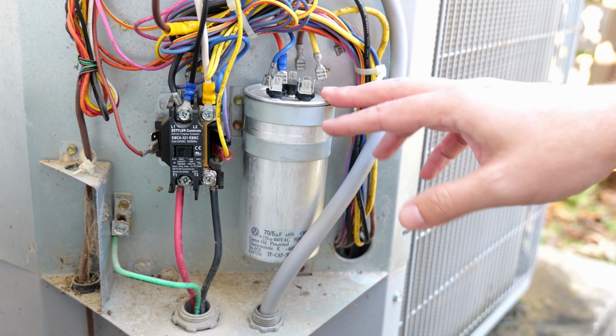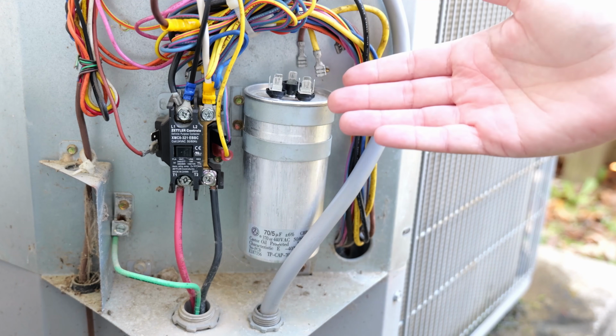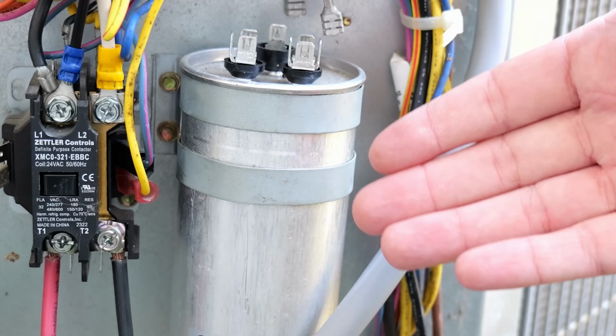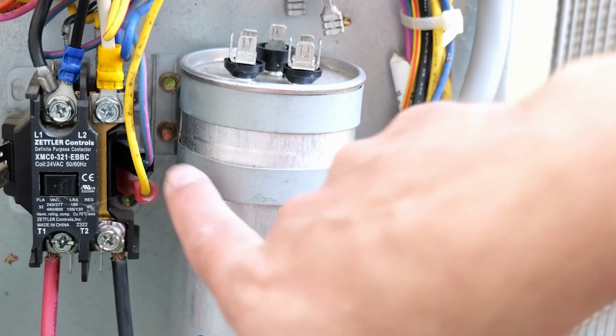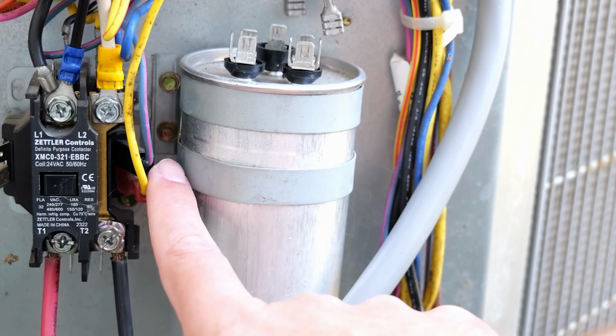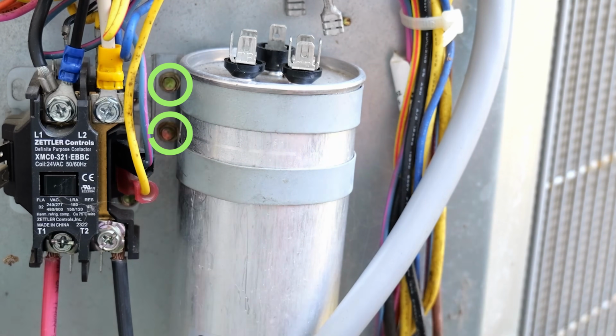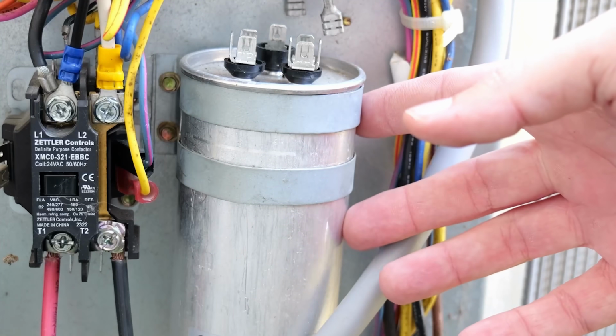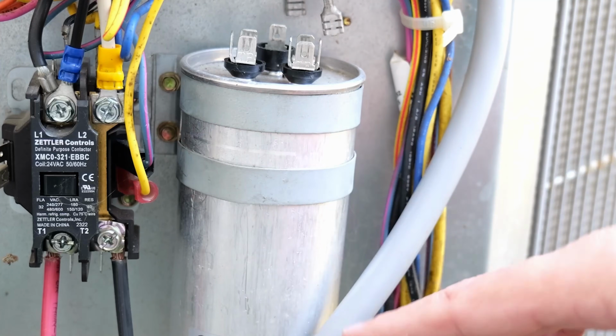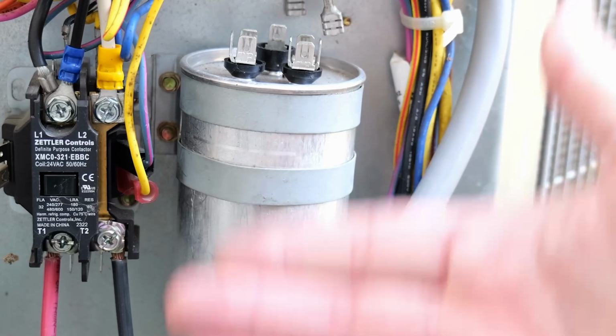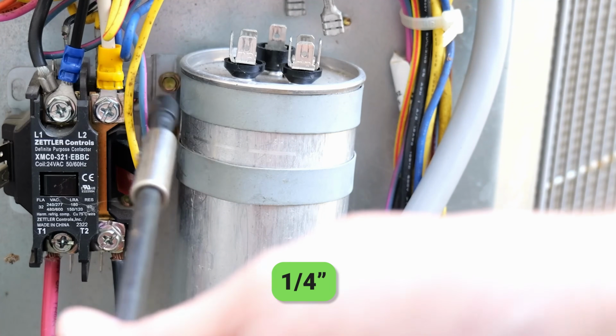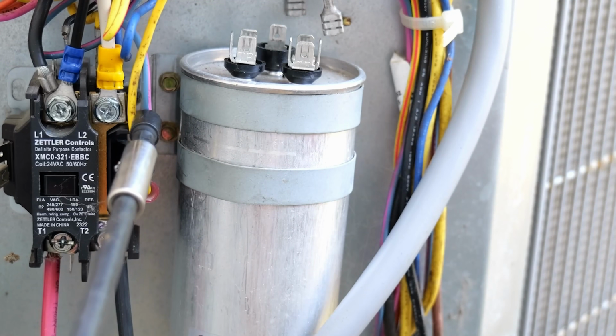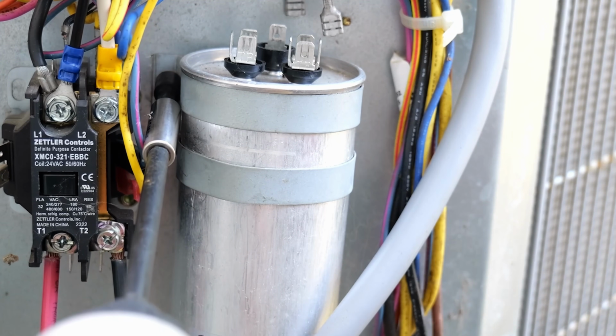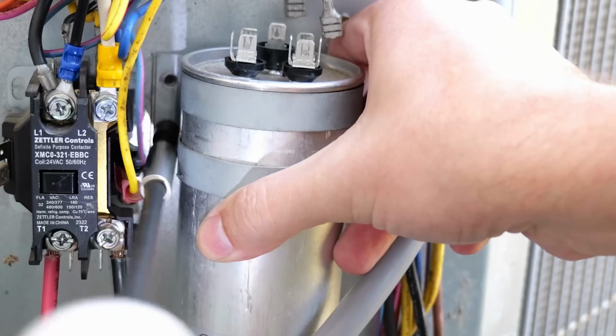All right, so now that I've shown you all of that up close, if I had found that this was a bad capacitor, that's when we now need to replace it. These are almost always being held in by these straps like this. They are mounted to the unit right back there. You see those two screws, top and bottom. So all we would need to do in order to replace this is remove those two screws. Those particular screws are 1/4 inch. Because they're kind of in there, kind of deep, I like to use an extension on an impact, have my 1/4 inch nut driver on it, and then I just remove those screws.